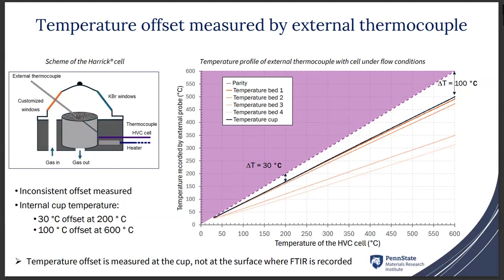And this is the maximum temperature you can achieve, because this is the temperature that is in contact to your powder. And we can see that even by doing that, we have a difference of 30 degrees Celsius at 200 Celsius set, and 100 Celsius when we set the temperature to 600 degrees Celsius. So this is a good approximation, but it doesn't tell us what is the temperature at the surface we're analyzing. It just tells us what is the temperature inside the cup.